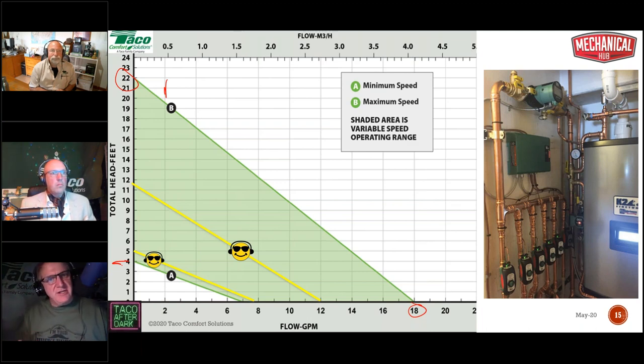Now, under design conditions, on that coldest day of the year, you're going to have this set up with a strap-on sensor on the supply pipe going out to the system, and another on the common return coming back from the system. The circulator will vary its speed to maintain the desired delta T within the system. In this case, we designed it to a 20. Let's try to maintain 20 for as much of the heating season as we can to mitigate short cycling. So let's say everything started up on the design day, the coldest day of the year.